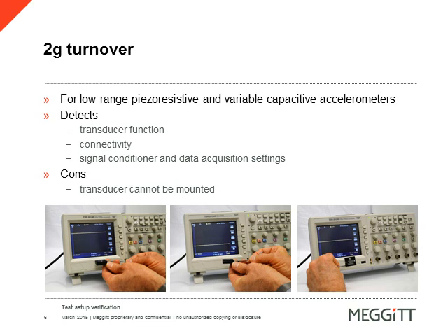Yes, Tim, thank you. As you mentioned, some high G transducers may not be tested at all by performing this 2G turnover test because the transducer's output is just too low. Additionally, this test method may require the sensor to be unmounted from the test structure, perform the 2G test, and then remount it again. This might be time-consuming. Performing this particular test method may be best done before final mounting.